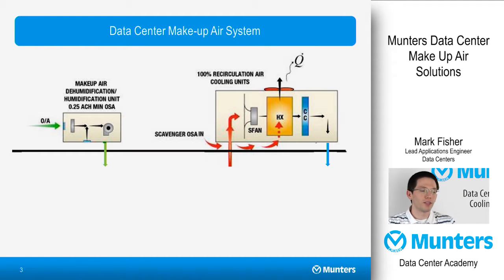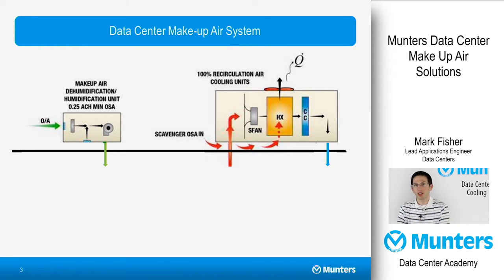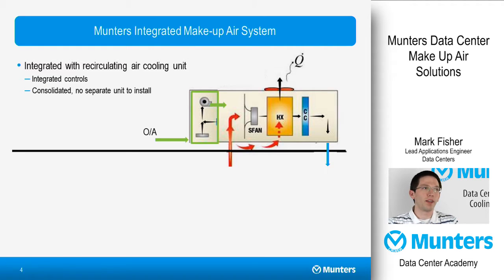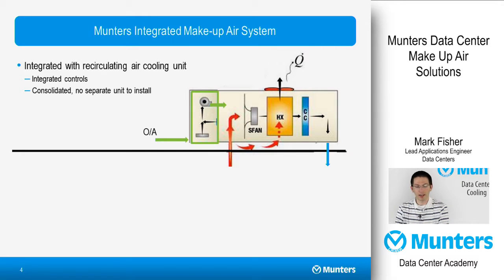In a typical air-cooled data center system there are multiple recirculating cooling units as well as separate dedicated makeup air systems. Munters is a market leader in dedicated outdoor air systems and has several energy-efficient approaches for this type of solution. In addition, Munters has a patent-pending integrated makeup air module that has several benefits including integrated controls with the main air handler, and it's consolidated so there's no separate unit, no separate wiring, and no separate duct penetrations.